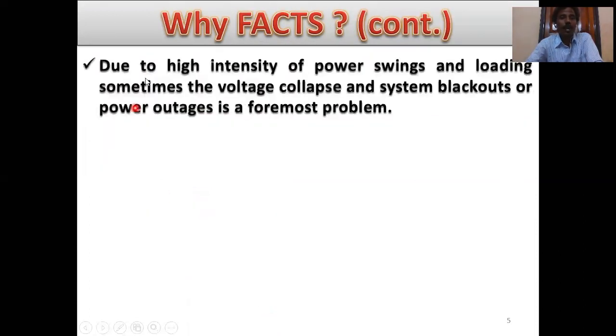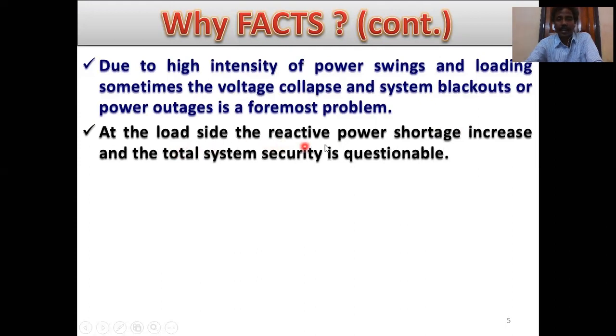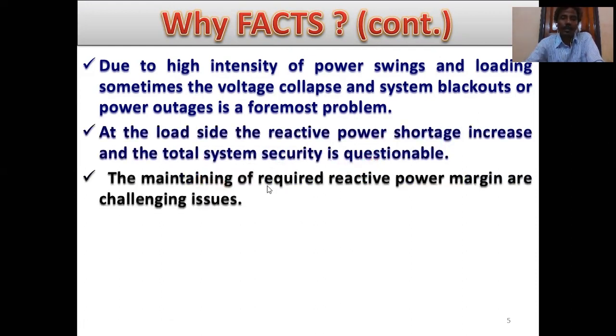So next, why FACTS continued. Due to high intensity of power swing and loading, sometimes voltage collapse and system blackouts or power outage is a foremost problem. This is also a very important issue, power blackout. At the load side, the reactive power shortage increases and the total system security is questionable. Maintaining the required reactive power margin is a challenging issue.